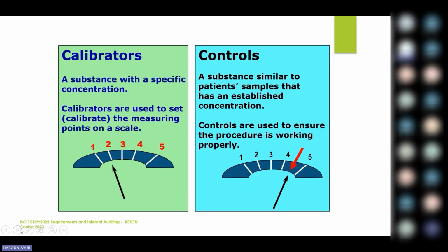And how do you know that our calibration is okay? So rarely do we know if calibrators are actually okay. For us, what we usually check in calibration is if an absorbance has been read, and if the curve has been drawn going in the direction the insert has said. So if it's an ascending reaction, a descending reaction, logistic 5P curve, if it's a linear curve. So all what we focus on in calibration is just checking if the right procedure has been done. But the control is what will tell you if your calibration is okay.